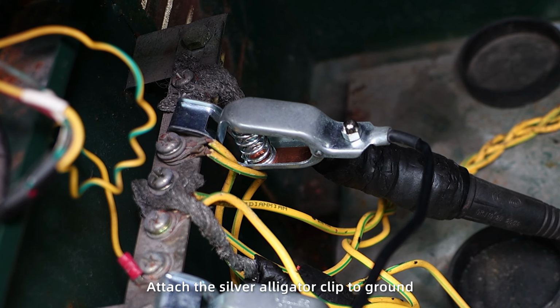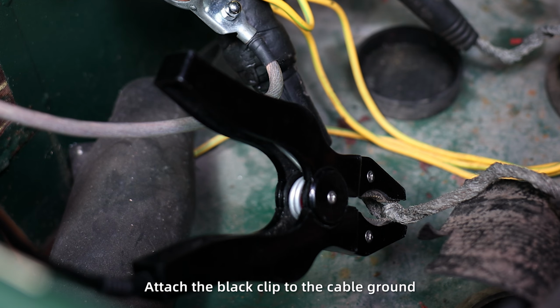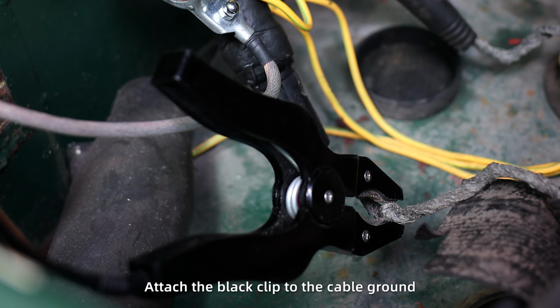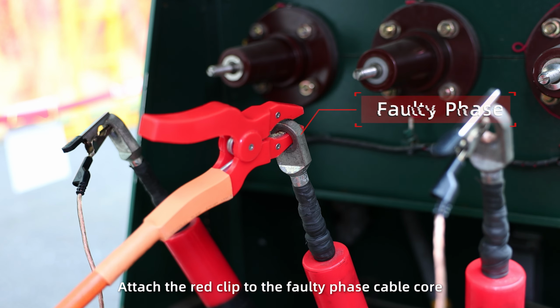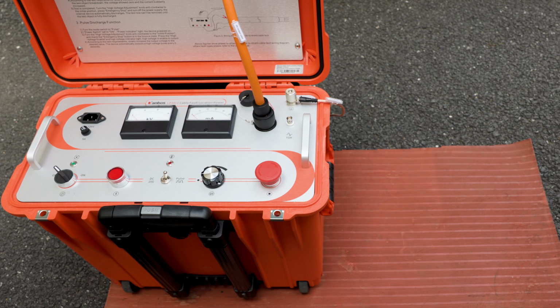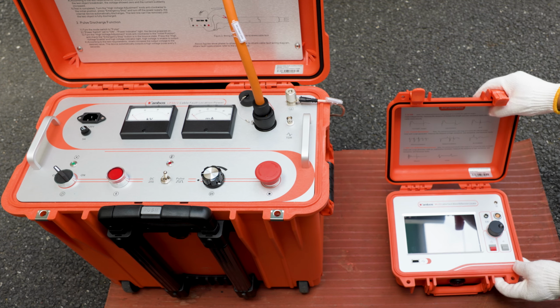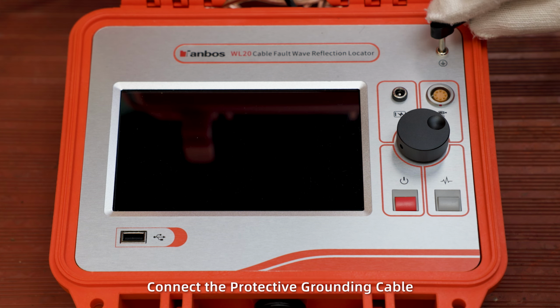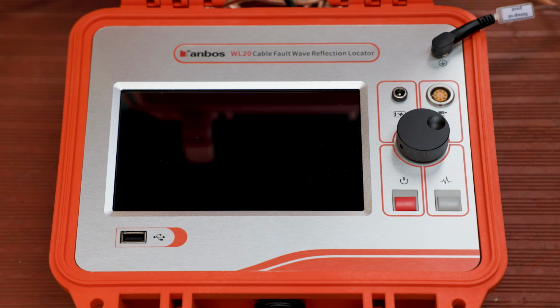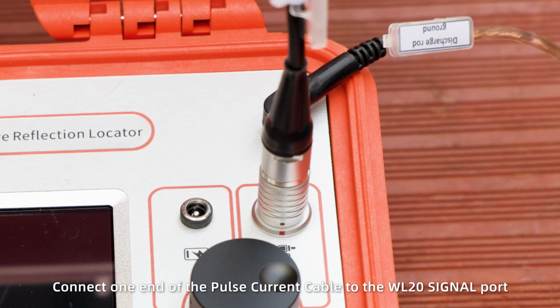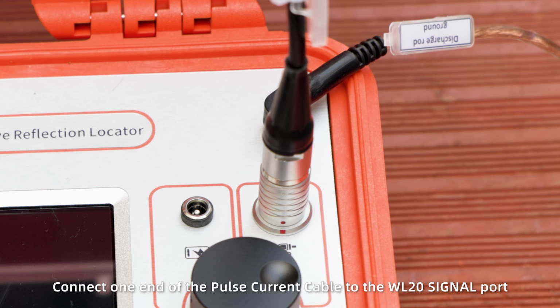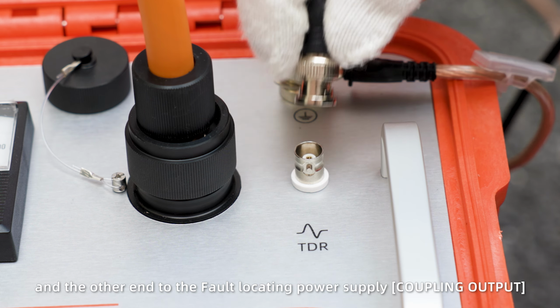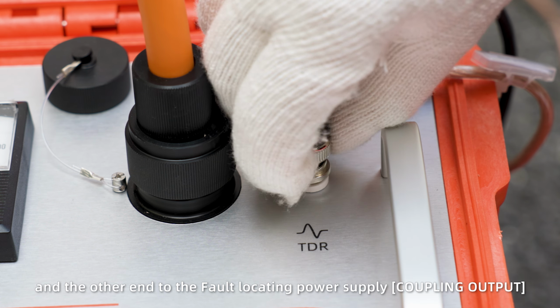Attach the silver alligator clip to ground. Attach the black clip to the cable ground. Attach the red clip to the faulty phase cable core. Connect the protective grounding cable. Connect one end of the pulse current cable to the WL20 signal port and the other end to the fault locating power supply, coupling output.